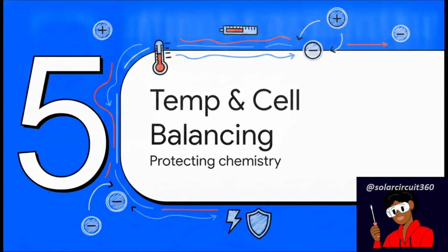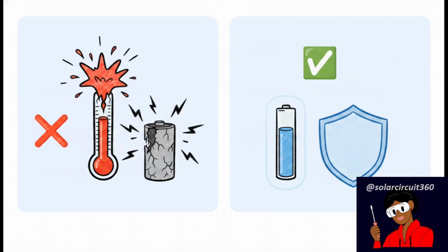Which brings us to Section 5, temperature and cell balancing. Next, we need to protect the internal chemistry of the lithium cells themselves, and we do that through strict temperature and balancing limits. Temperature settings are incredibly important, yet people ignore or bypass them all the time. Lithium cells like to operate within very specific approved temperatures. Disabling your temp protection just to avoid an annoying system shutdown is wildly dangerous.